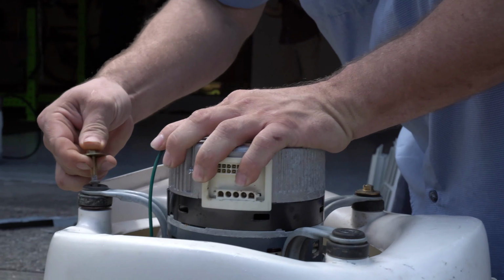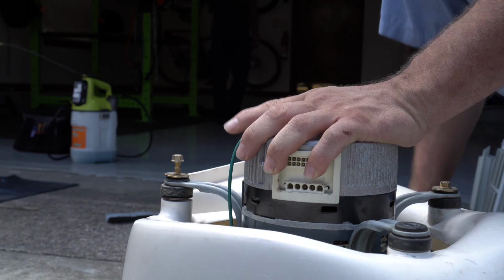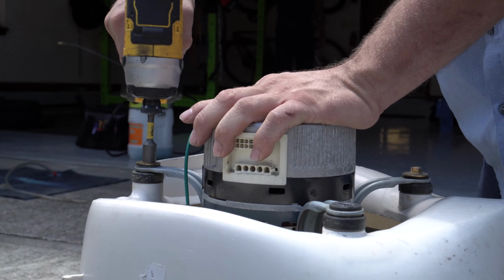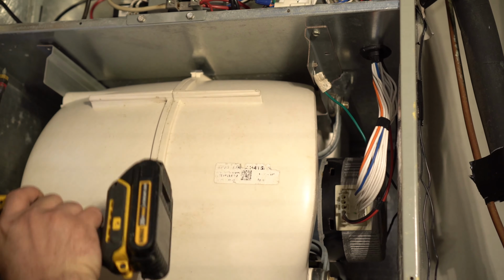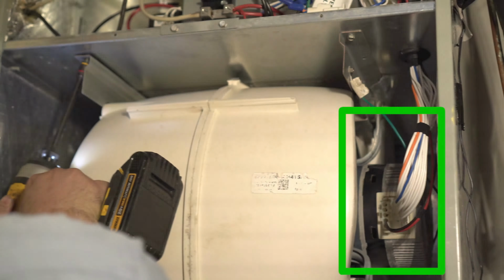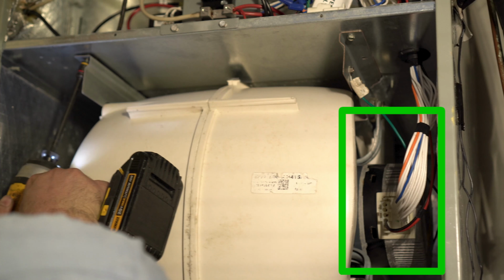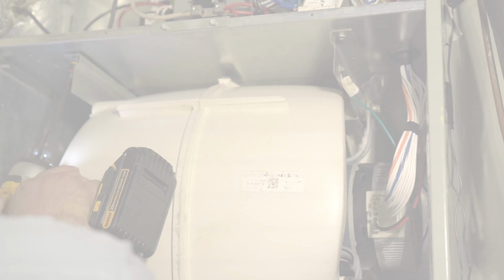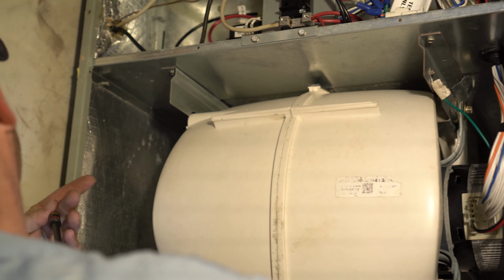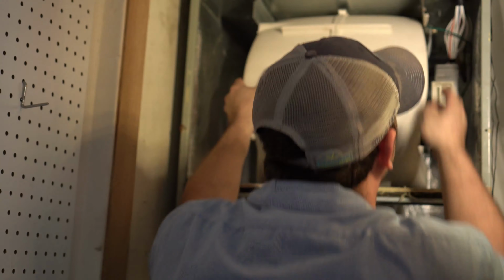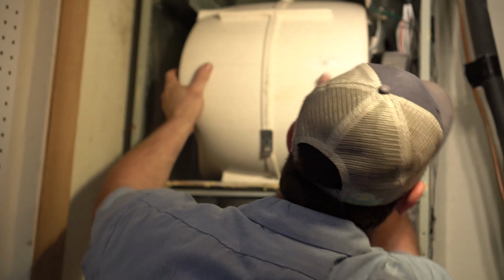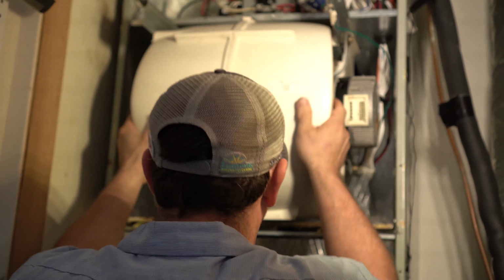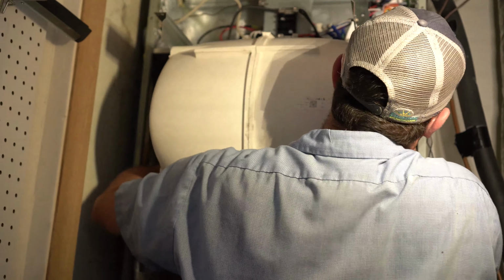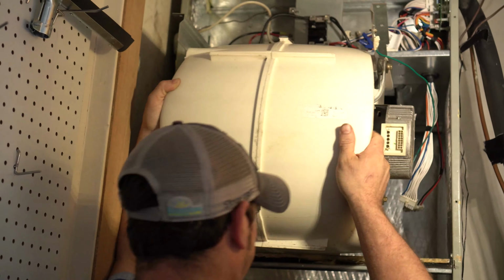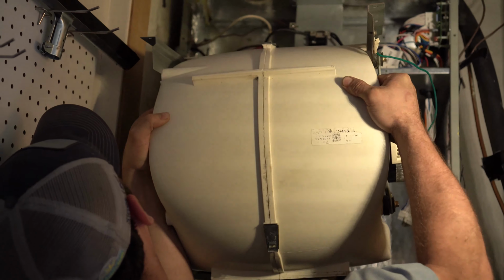It is important to mark your wires for easy reference and safety. In this video, we will go over how to properly mark your wires. Step 1. Before you remove the motor, mark the location of the wiring on the side of the blower housing so that when you reinstall later, the wiring is in the correct position. Step 2. If the motor utilizes a plug, there is no need to mark the wires. If you have to remove the wiring from the board in the upper portion of the air handler, make sure that you take a picture with your phone or mark the wires with tape or Sharpie so that you know exactly which terminals to reinstall to.